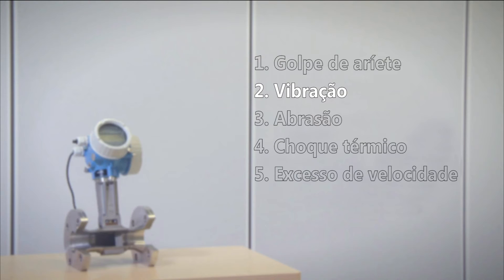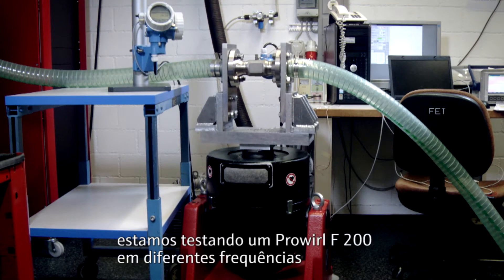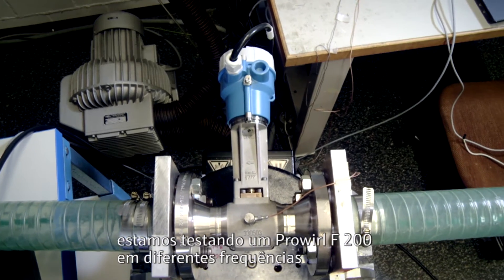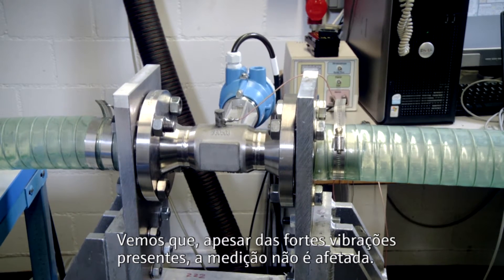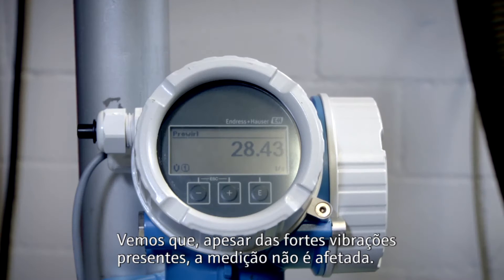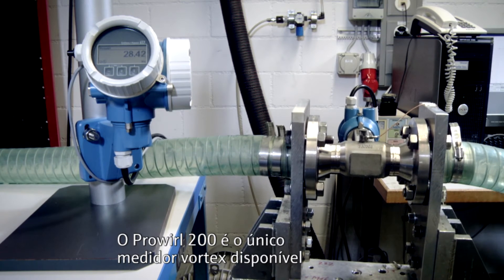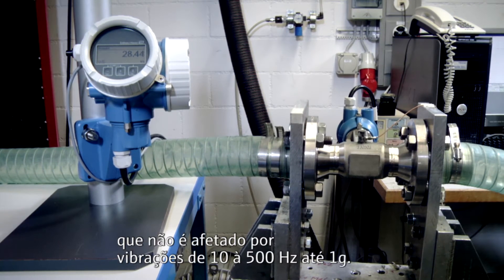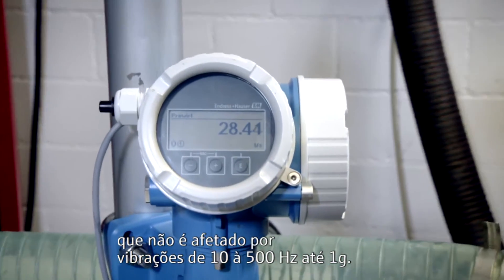Test 2 – Vibration. On this vibration rig we are testing a Prowirl F 200 at different frequencies and accelerations of different levels. We see that the measurement is not affected although strong vibrations are present. ProWhirl 200 is the only vortex device available that is unaffected by vibrations from 10 to 500 Hz up to 1 G.